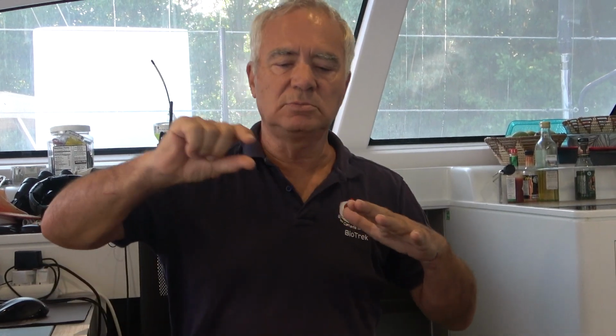That brings back the original point: any charge source, any discharge source to a certain extent, but especially the charging, has to be controlled. You can't just look at the top voltage. You might push the maximum amps the device allows to charge the battery as quickly as possible, and as it approaches the battery's high voltage, the amps will start to reduce. But that's only part of the system.